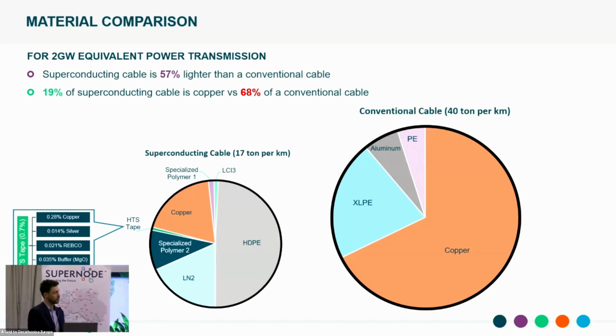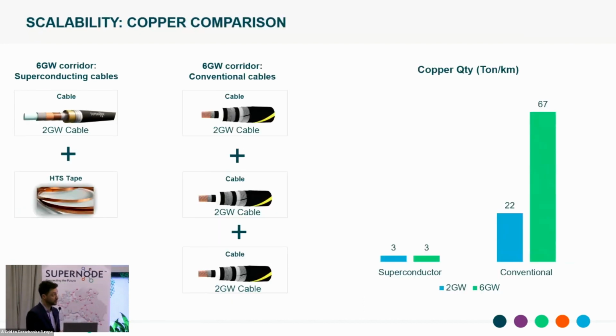So there's no significant impact on the geometry or the cost of the cable, and we can scale this technology to very high power capacities, which you can't do with copper, and that's what we're presenting here. For example, for SuperNode, we have a baseline design, a 2 gigawatt cable. We can easily convert that into a 6 gigawatt cable by adding more tape. There's no impact on OPEX, and very little impact on cost. Whereas if you were to do that with copper, you'd essentially need more of these systems, multiple 2 gigawatt cables, to deliver that power corridor. So superconductors are scalable and a very efficient way to deliver high capacity power corridors.